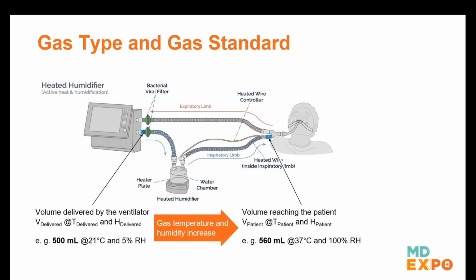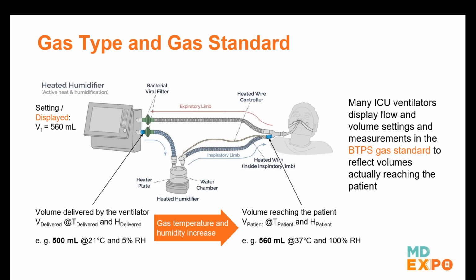So now what the patient is actually getting is a volume that's more than 10% higher than what the ventilator is delivering, okay? In the old days, ventilator operators, therapists, had to do that calculation themselves. They had to look at their patient and say, I want to deliver 500 mils to them, but then they wouldn't punch in 500 mils, they'd punch in something lower, right? In this case, if they want to deliver the 560 to their patient on this particular ventilator, it's going to display in BTPS. Okay, so its display will tell them what is going to happen to the gas by the time it gets to the patient, not what is actually being delivered from the outlet of the ventilator. Does that make sense? Okay, so many ICU ventilators do use BTPS as a gas standard. That makes it convenient for the operator so that they don't overinflate their patient's lungs. Patient safety, right? Number one for all of us.